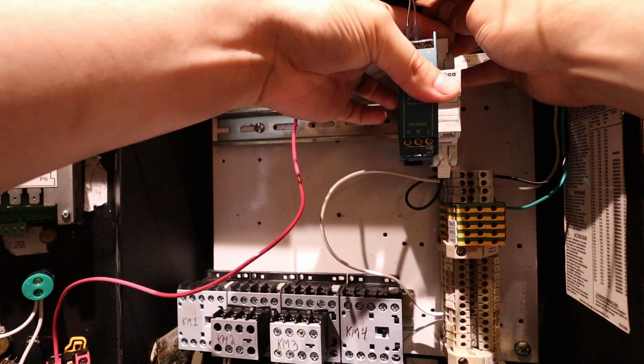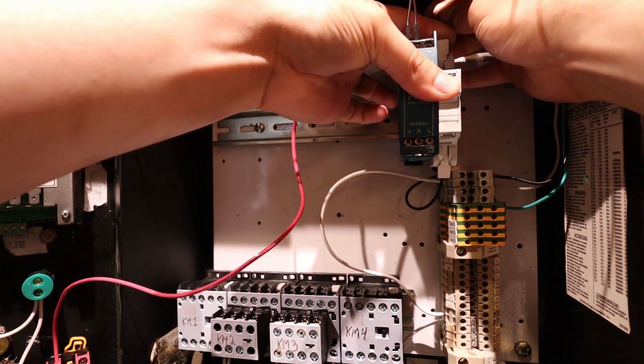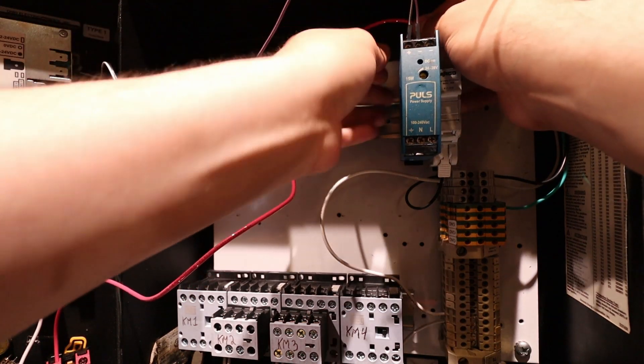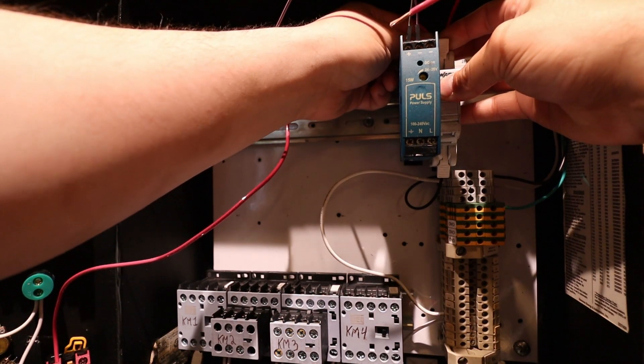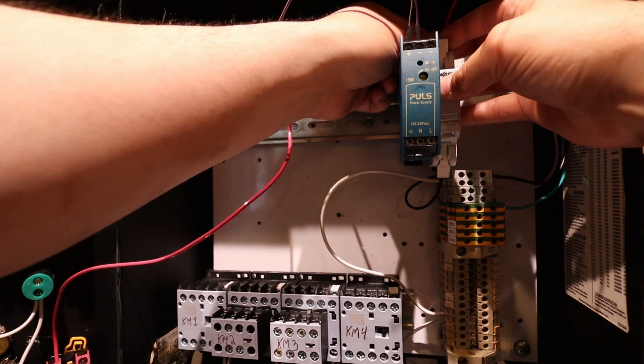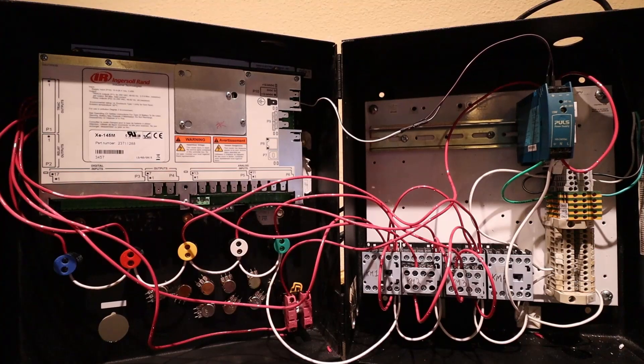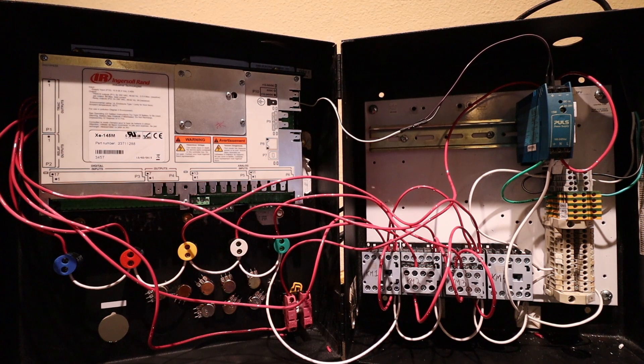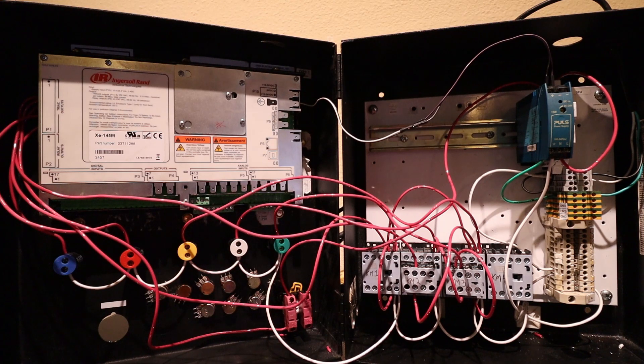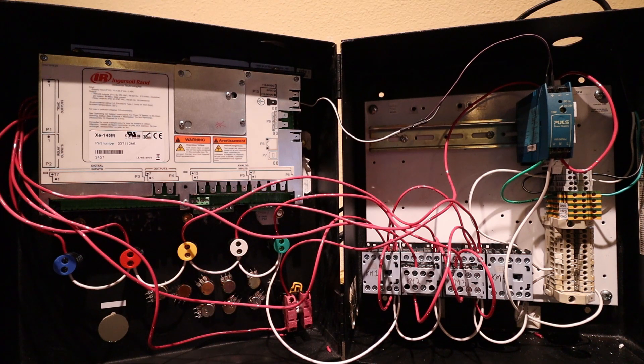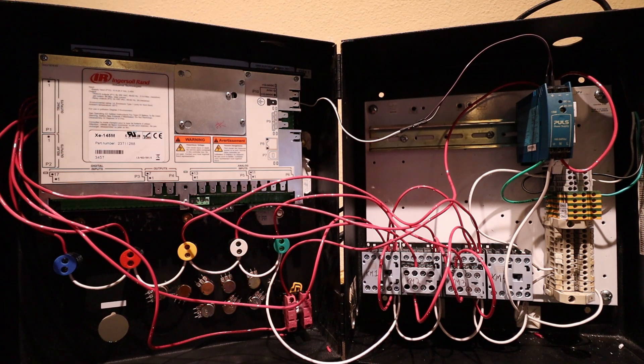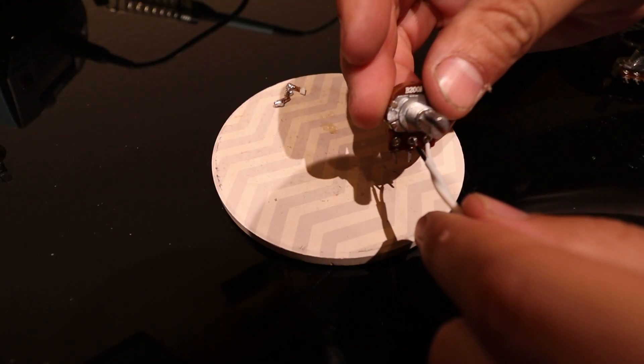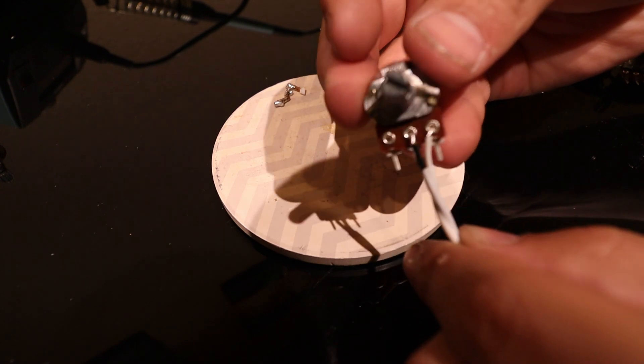They got the 120 volts neutral, all they need is the hot which I'm connecting up on top. The other end of the hot is coming through the top of the fuse. One end of it is going to go to the 120 volts AC to 24 volt DC power supply to power the DC for the controller. There's also going to be another wire coming out the top of the fuse to go to the controller, and all the wires coming out of the top left of the controller are going to be firing off to power all of these indicator lights and the contactors that they're connected to. You can also see one of them's going through the e-stop on the bottom right of the left side of the panel to cut off the 120 volts going to all the solenoids and the contactors if you hit the e-stop.